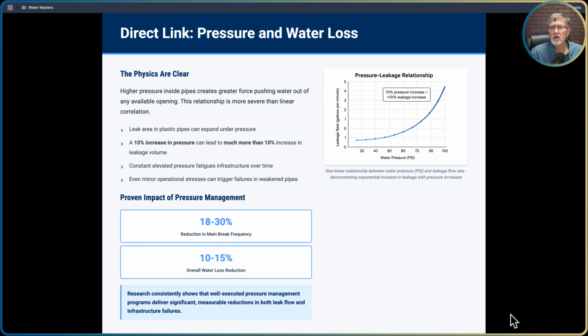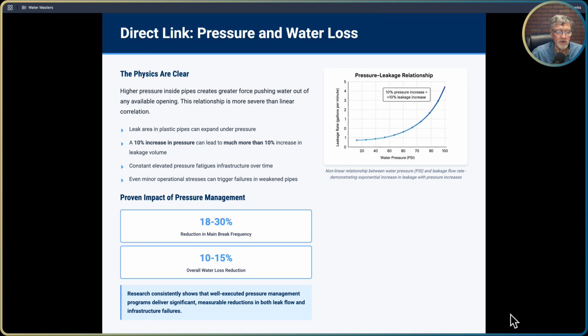And constant elevated pressure fatigues infrastructure over time, and even mild operational stresses can trigger failures and weaken pipe, especially as this overpressurization continues at night and then during the day. Then you back off a little bit, then it's overpressurized again at night. Going through those cycles really creates a lot of stress on your system. So the proven impact of pressure management: we've seen an 18 to 30% reduction in main break frequency, and 10 to 15% overall water loss reduction. Research shows that well-executed pressure management programs deliver significant, measurable reductions in both leak flow and infrastructure failures.